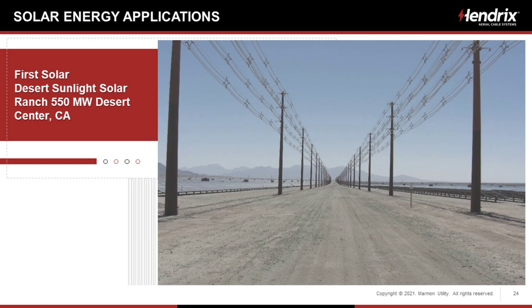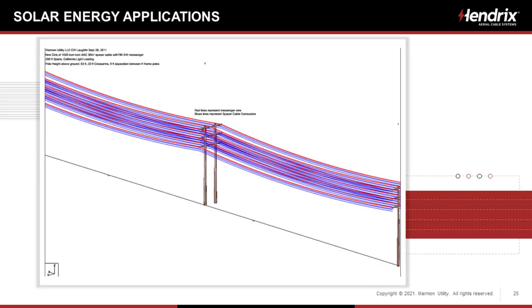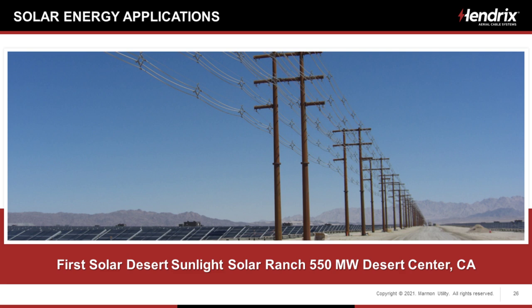Here's First Solar Desert Sunlight. Solar Ranch, this is now owned by Berkshire Hathaway Energy. A lot of these facilities have flipped owners. This is a 550 megawatt facility. We put 50 megawatts in each of 11 collection circuits. And this is running right up to the substation, standing at the substation, looking out, if you will. We've done designs with 14 collectors on one pole line.